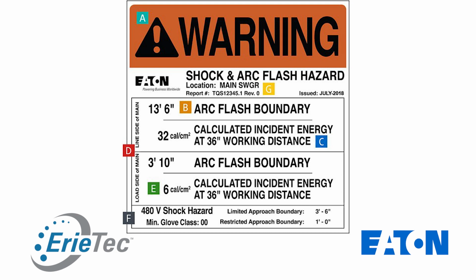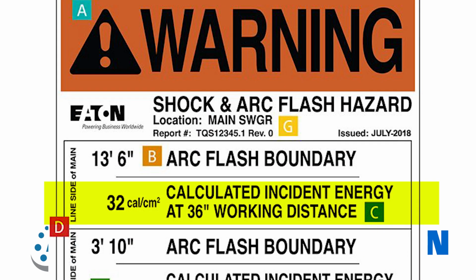Three, being the available incident energy level, the minimum arc rated clothing, or a site-specific PPE. The available incident energy level and the corresponding working distances, right, which is part of the approach boundaries. Minimum arc rated clothing or the site-specific PPE. Your employer may have listed out guidelines for what they want personnel to wear when they're working on the equipment live. So those things need to be adhered to and should be on the label.